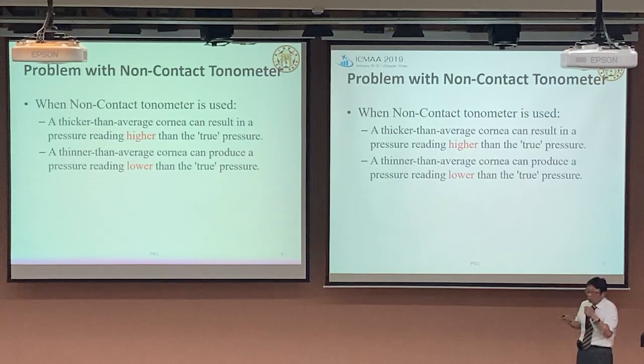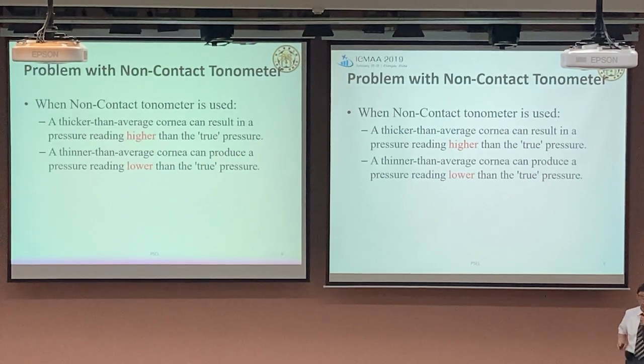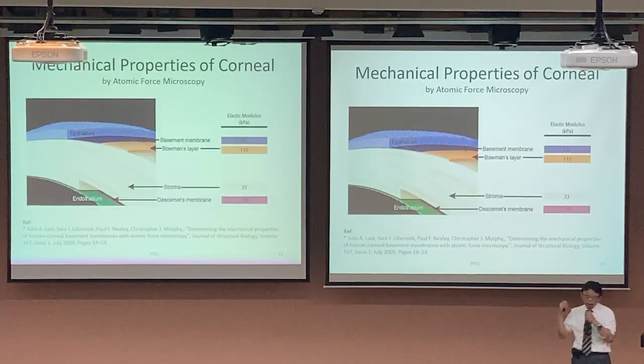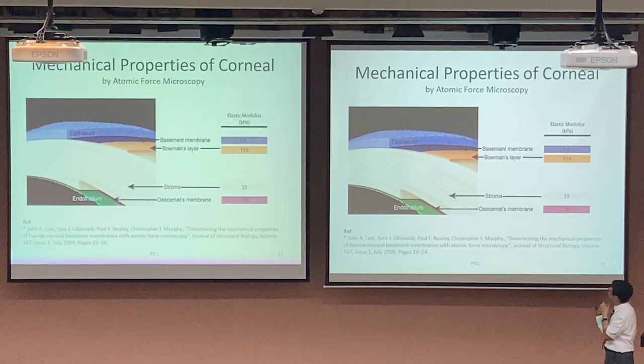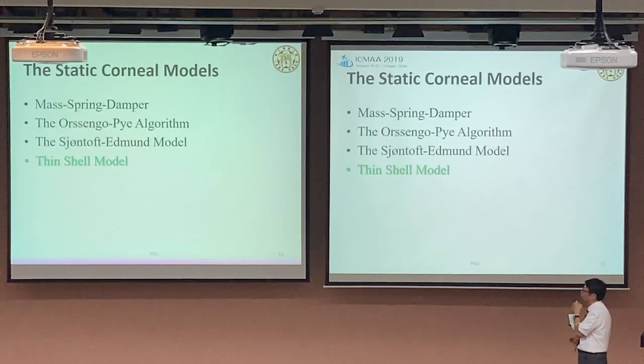Now, the non-contact tonometer, like I already described, does not work like when you drop the hammer on your eye, because that achieves a dynamic balance, so the pressure is correct. But in this case, everything is moving, so you try to estimate the differences, and many times your measurements are very dependent on the stiffness and mechanical properties of the cornea. The cornea itself has a very complicated structure. It has layers of different materials, and usually I believe the stroma occupies the bulk of the cornea, but there is also a layer, Bowman's layer, which is the strongest layer. So this one single layer determines the stiffness of the cornea. Well, this is just background material, so let's not worry about that.